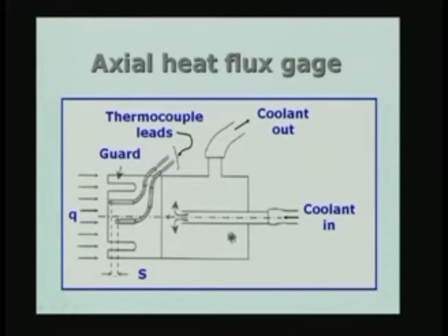Another point which I would like to mention here is that if we control the rate of coolant which is being sent into the back of the probe, that is, if I control the amount of coolant by having a valve which is controlled by the temperature indicated by, let us say, the first thermocouple. This first thermocouple is very close to the surface, and therefore, it is an indication of the surface temperature.